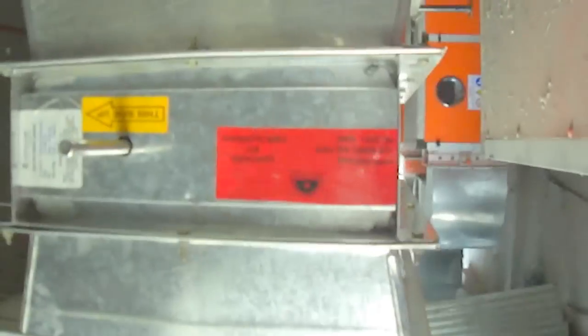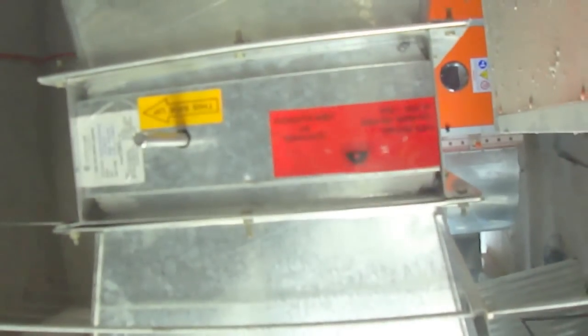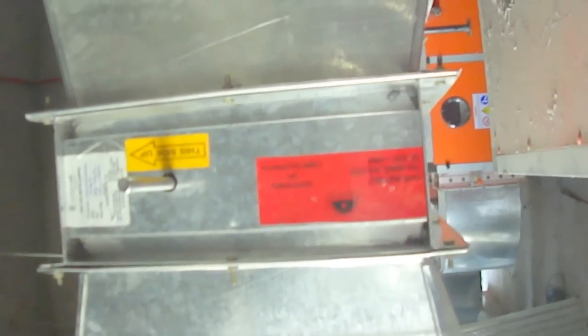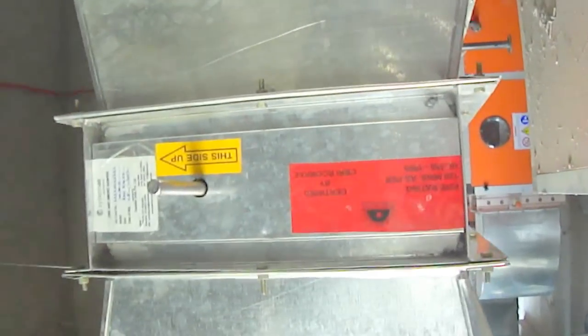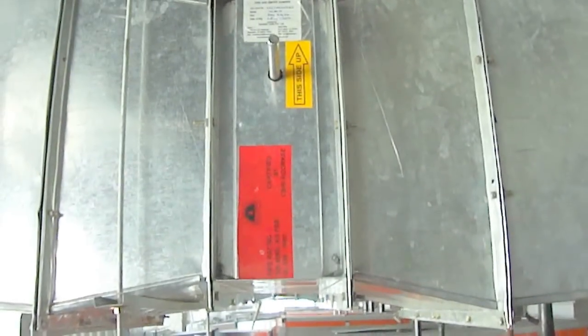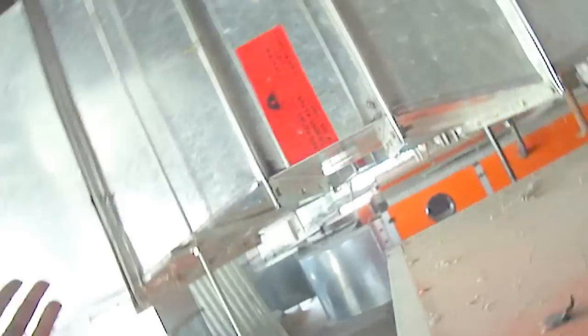Yeah. So next you see here, this is an inlet to the AHU air side. The return we can call, as this is a return duct. Fine. And since many AHUs are available, return duct is a must. If I do not use the return duct, what happens? It will take the air from somewhere, from some area. So return is a must. If it is only a single AHU room, then if you want, you can avoid the return. Only an opening is enough. But here there is a series of AHUs. So this is a return line, and again, what is that? I think we can identify this one.